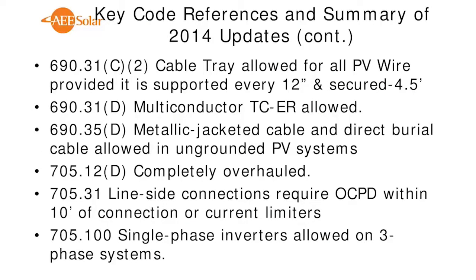We're going to talk about rapid shutdown, which started in 2014 as the conductors leaving the array. In the 2017 code, we'll actually cover shutting down within the array itself, or reducing the shock hazard, which is really the key concept there. We talked about combiner disconnects yesterday and things like that. Cable tray, multi-jacketed cable, multi-conductor cable, metal jacketed cable, all fun stuff.